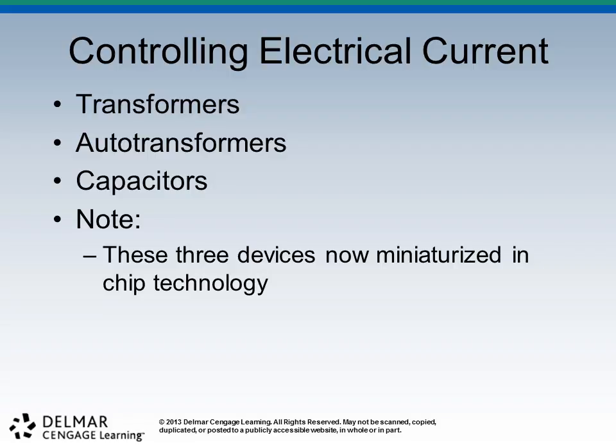We're going to use that way to the left for a different thing. We use the step-up transformer, which I described. The auto transformer we're going to use to adjust the voltage of the incoming AC waveform so that we can eventually use it to create kVp later. But that's not what it's for right at this point. It's just going to adjust or smooth out the voltage for us. But like I said, I'm probably getting ahead of myself.